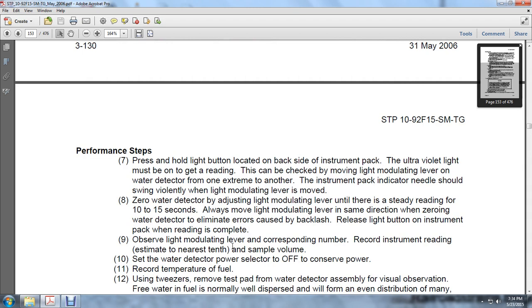This can be checked by moving the light modulator lever over the water detector from one extreme to another. The instrument pack indicator needle should move violently when the light modulating lever is moved. Zero the water detector by adjusting the light modulating lever until there is a steady reading for 10 to 15 seconds. Always move the light modulating lever in the same direction when zeroing the water detector. This eliminates the error caused by the backlash.